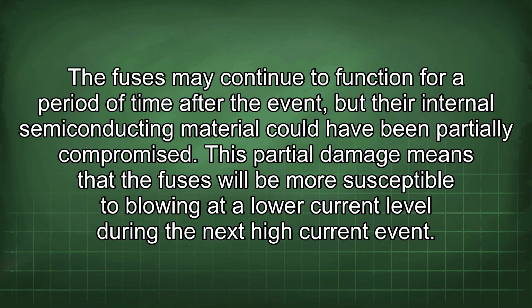The fuses may continue to function for a period of time after the event, but their internal semiconducting material could have been partially compromised. This partial damage means that the fuses will be more susceptible to blowing at a lower current level during the next high current event.